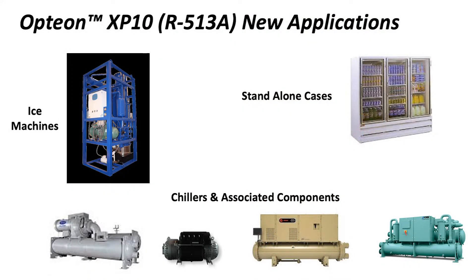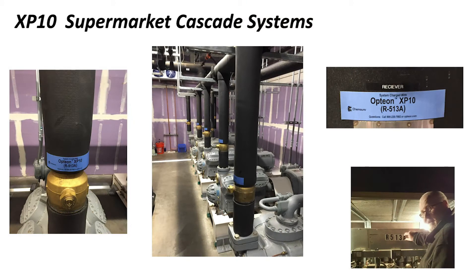That similarity gets us into some of the applications where R513A has been used. It's a direct replacement for R134a in a lot of equipment that was designed based on R134a, where OEMs wanted to transition and have a lower GWP offering — going from 1,200 down to less than 750, as needed for air conditioning under some proposed regulations. R134a chillers can easily be adapted and perform very similarly when charged with R513A, and there have been a lot of retrofits of those types of systems.